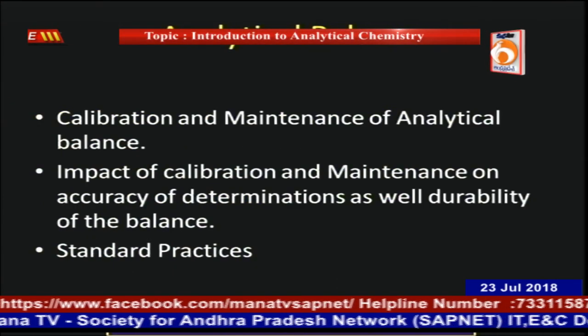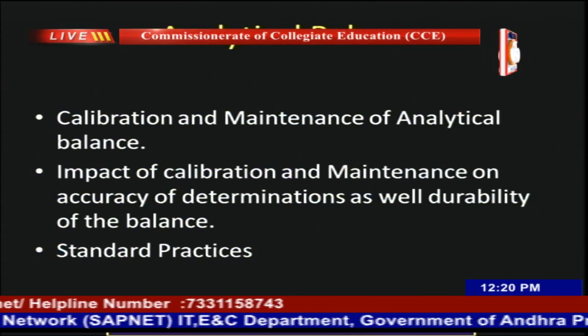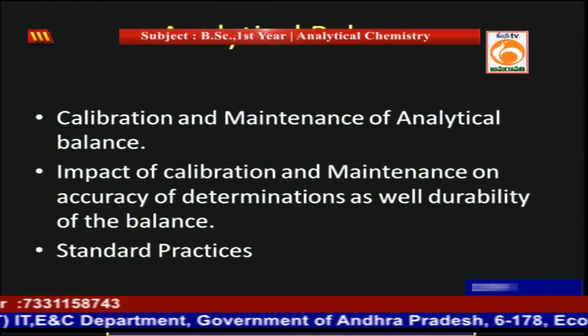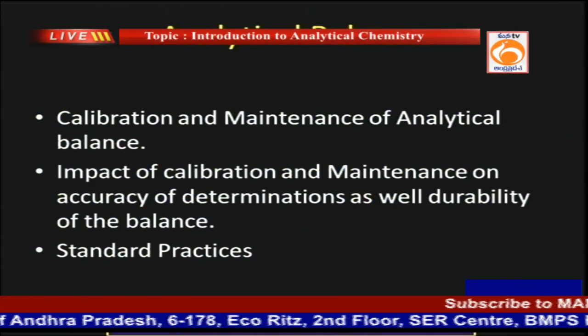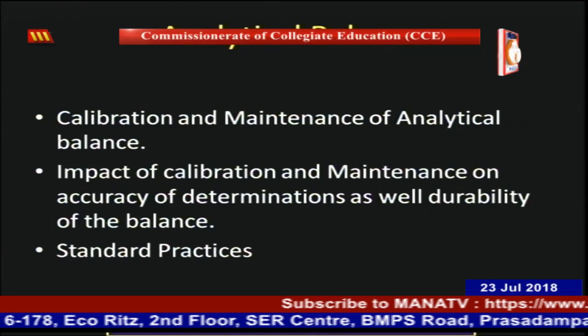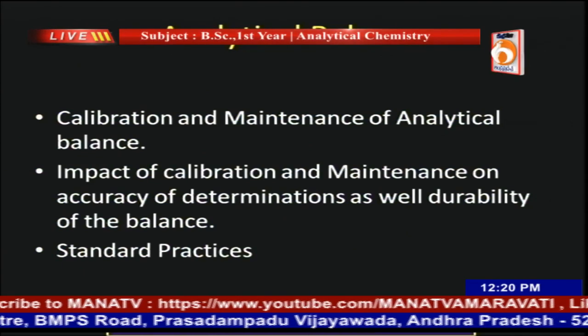Calibration and maintenance of the analytical balance you always do with the help of standard weights which are already calibrated, number one. Number two, the supplier of the instrument will also give a calibration certificate to you. You need to cross-check that. When the time is over, you have to get it done properly so that the validity and accuracy of the instrument will increase.